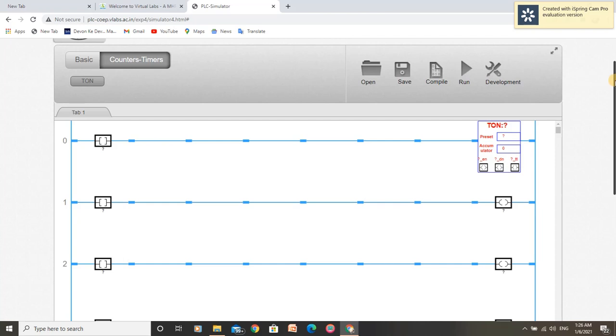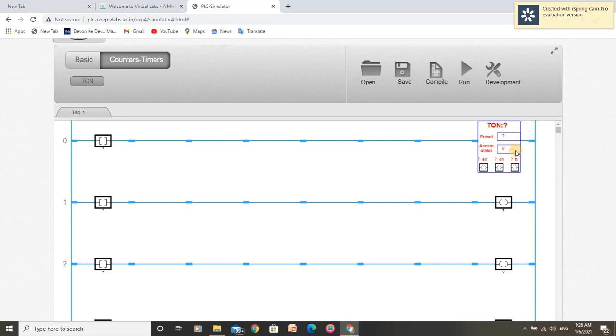The enable bit tells us that the timing operation is enabled by giving input from the push button. The timer timing bit tells us that a timing operation is in progress. The done bit is on when the preset value is reached from the accumulator value.